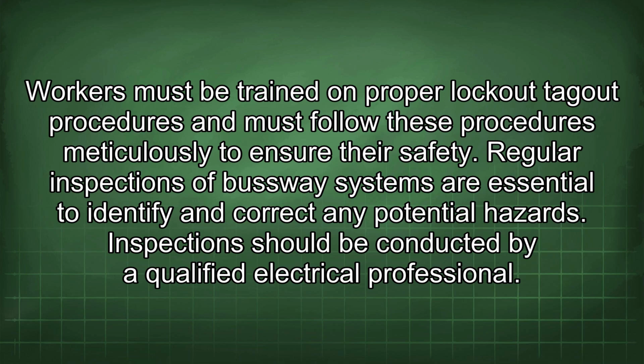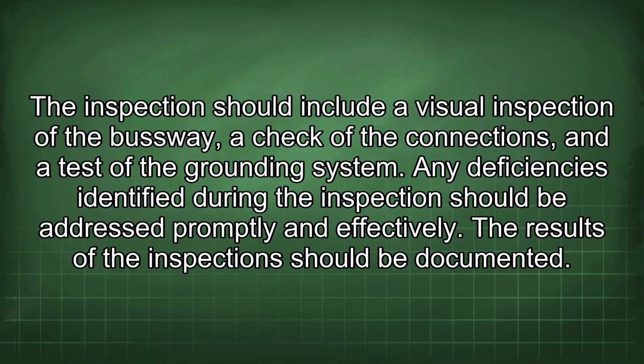Regular inspections of busway systems are essential to identify and correct any potential hazards. Inspections should be conducted by a qualified electrical professional. The inspection should include a visual inspection of the busway, a check of the connections, and a test of the grounding system. Any deficiencies identified during the inspection should be addressed promptly and effectively. The results of the inspection should be documented.